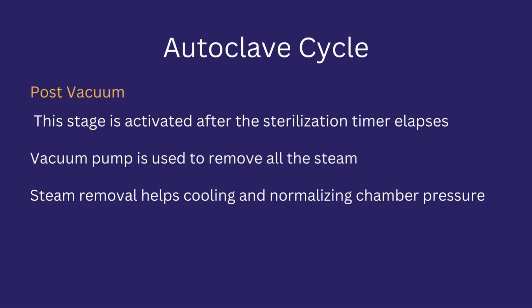Post vacuum. Post vacuum is the last step in the process, and this stage is activated after the sterilization timer has elapsed. In this stage, steam is removed from the chamber through the vacuum pump. Steam removal through a vacuum pump facilitates cooling and normalizing chamber pressure.